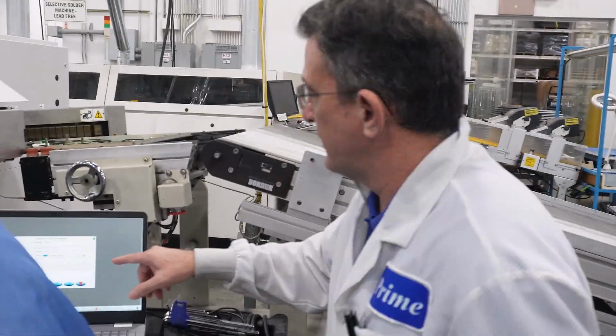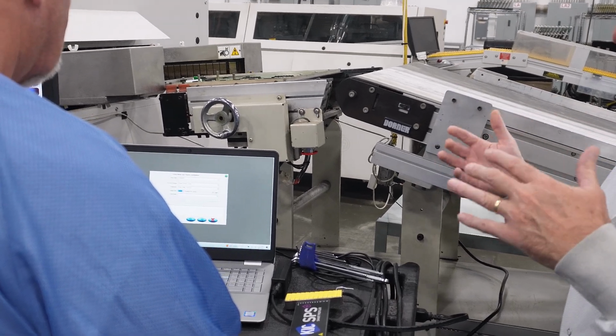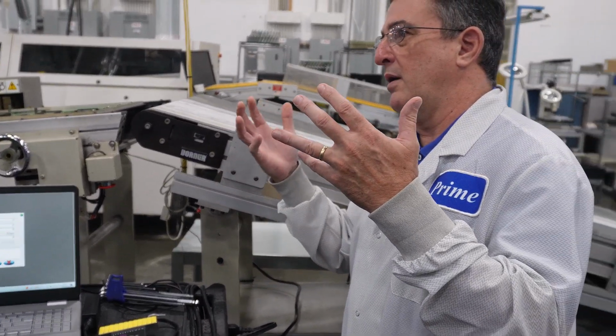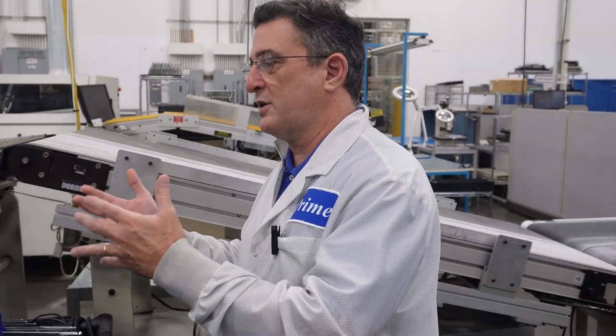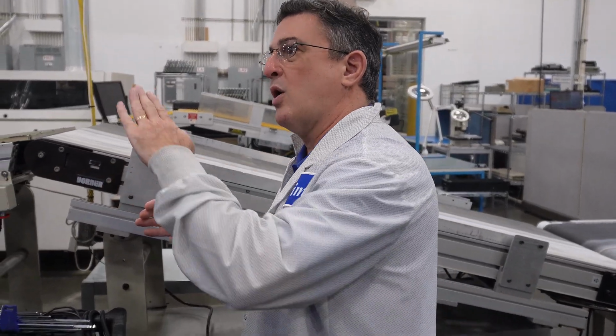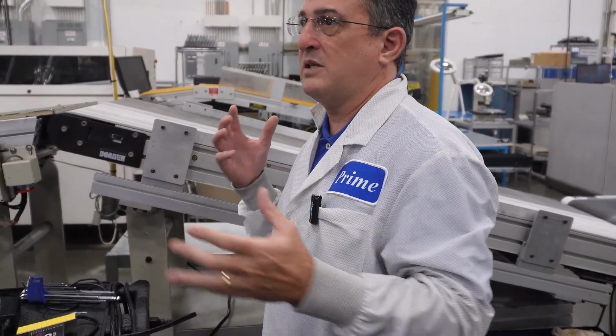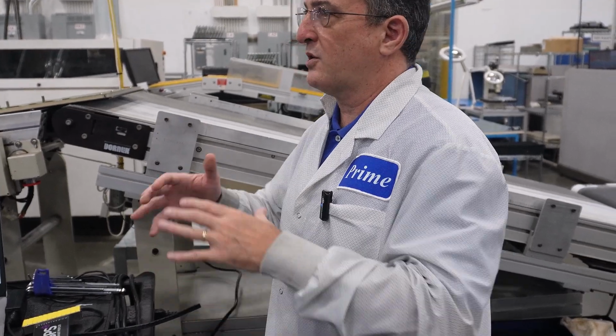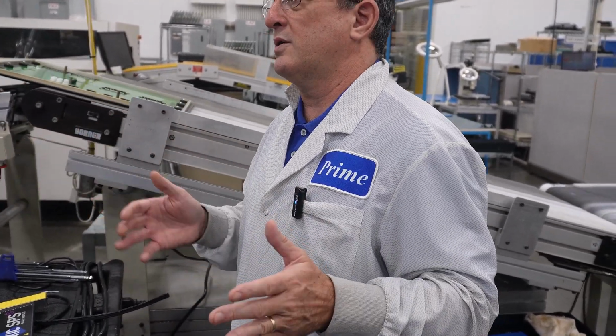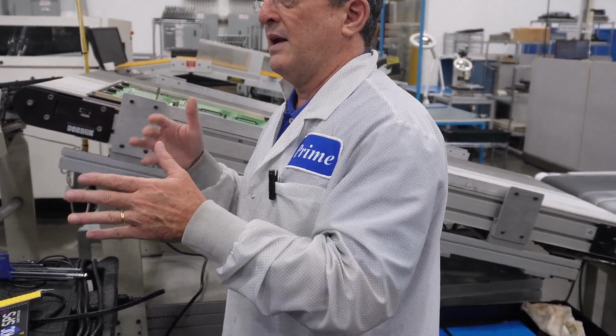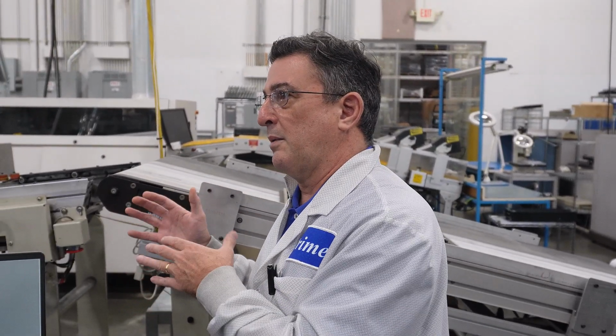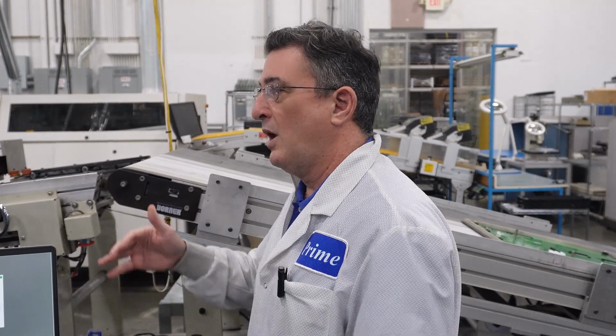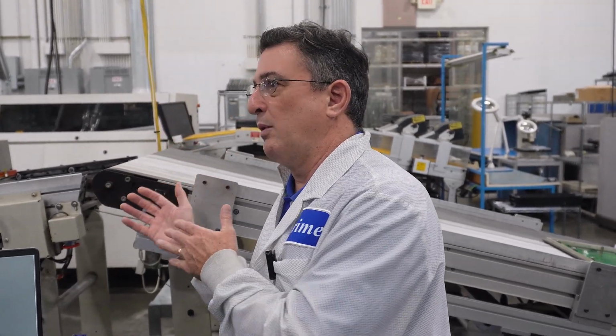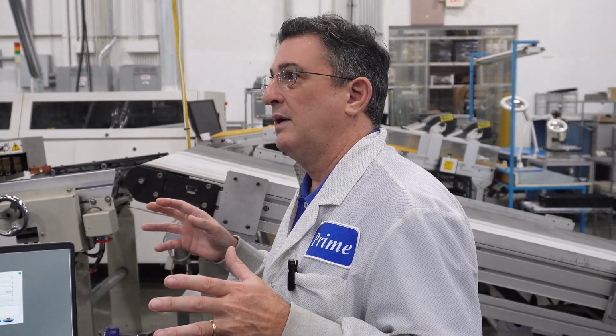We also have 2 more triggers. Click on that. This is built in behind the scenes. It's another benefit that we give the operators, the customer, to ensure that the profile goes all the way through the process. So if we have a failure where a TC may come off or the board may fall off in the process, if we don't hit these triggers, it'll say this profile is invalid. It's kind of like a safety mechanism to let the process engineers know that the profile didn't go through the process the way we expected it to. It would throw up an alarm message and label that profile a bad profile. And then we'd go in and analyze.